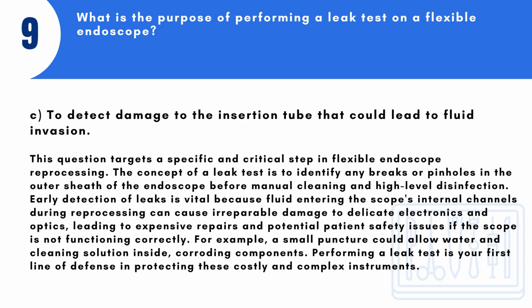Early detection of leaks is vital because fluid entering the scope's internal channels during reprocessing can cause irreparable damage to delicate electronics and optics, leading to expensive repairs and potential patient safety issues if the scope is not functioning correctly. For example, a small puncture could allow water and cleaning solution inside, corroding components. Performing a leak test is your first line of defense in protecting these costly and complex instruments.